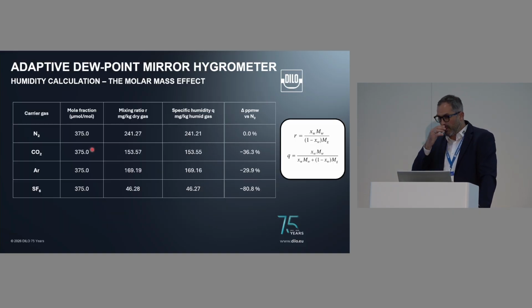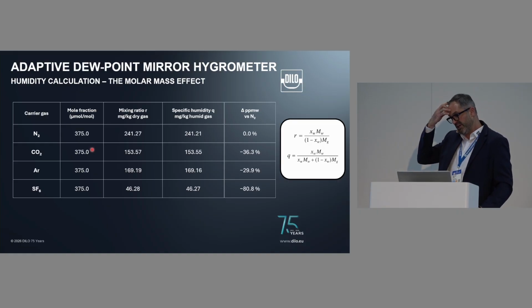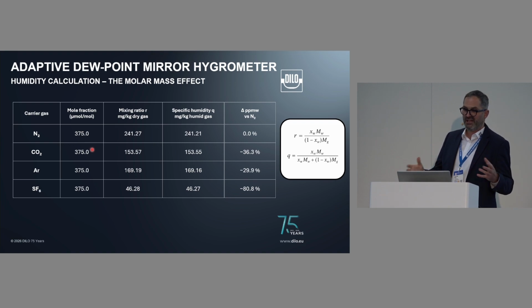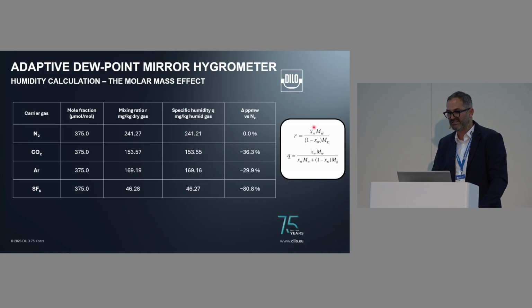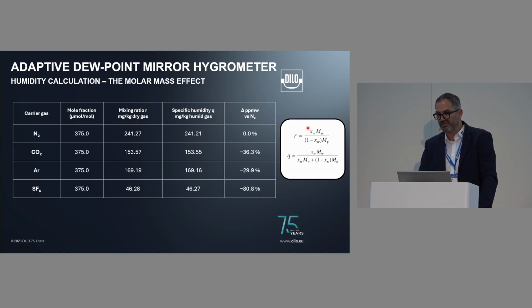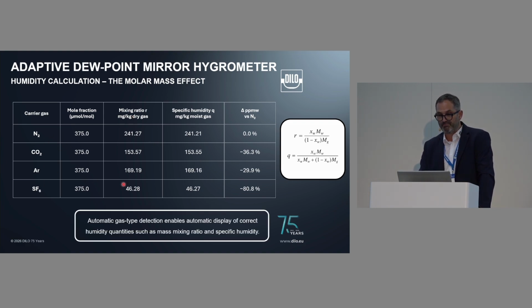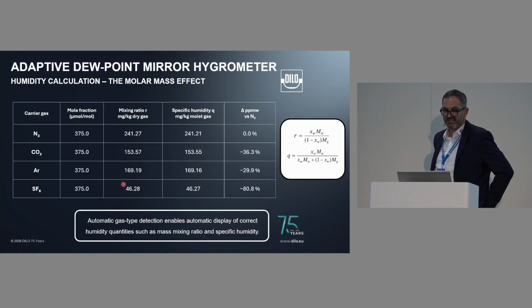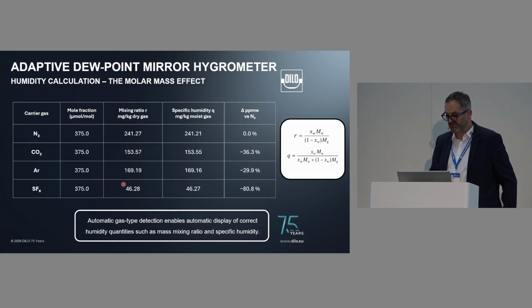Another important thing is that in a classical chilled mirror hygrometer optimized, let's say, for nitrogen or air, when it shows other parameters like the mass mixing ratio or specific humidity, those quantities depend on the molar mass of the gas. So here are the equations. We have the mass mixing ratio, for example, with the molar mass of water but also the molar mass of the gas. By measuring the gas type, we know the molar mass of the gas and can always display the correct quantities on the device, such as the mass mixing ratio and the specific humidity. So automatic gas type detection enables automatic display of correct humidity quantities such as mass mixing ratio and specific humidity.